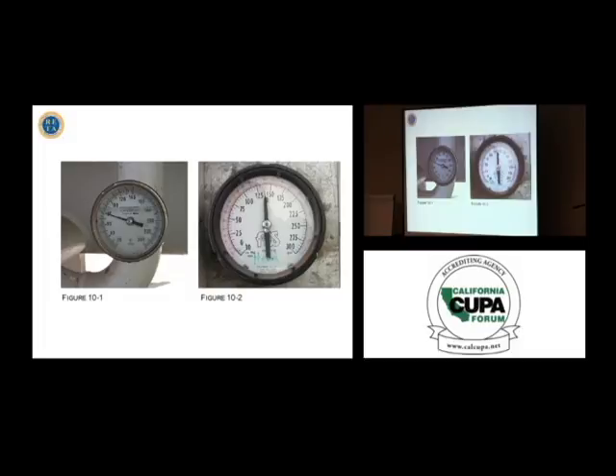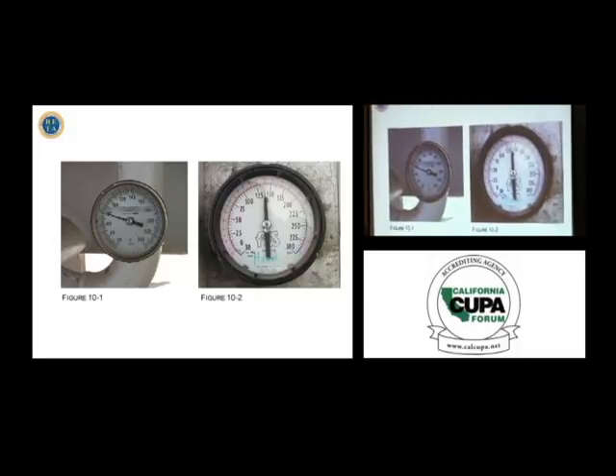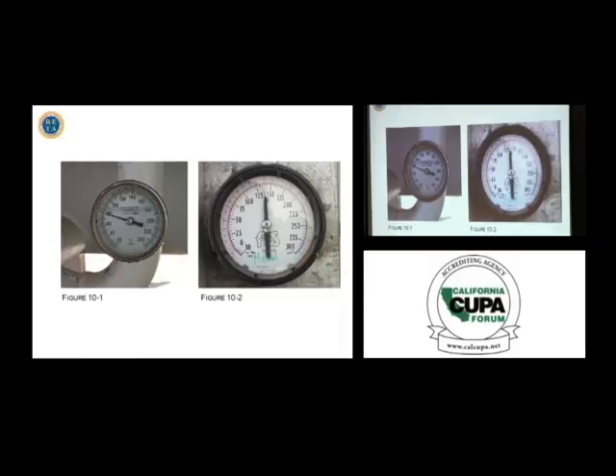Temperatures and gauges. One of the things that we're always concerned about is what is our head pressure, and is our head pressure what it should be? Is there another gas, a non-condensable gas, in my system that is causing the pressure from the discharge of the compressors to be higher than it should be? And so we're looking at, are we in agreement with the temperature of our condensate coming out of the condenser and the condensing pressure? Not the head pressure in the engine room, but the pressure out there at the condenser, because we could have pressure drop between compressor and condenser. So we're looking for agreement here with pressure and temperature, and when it's not right, we have to decide when is the time to purge.